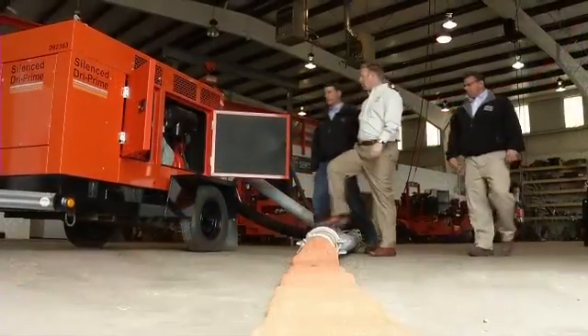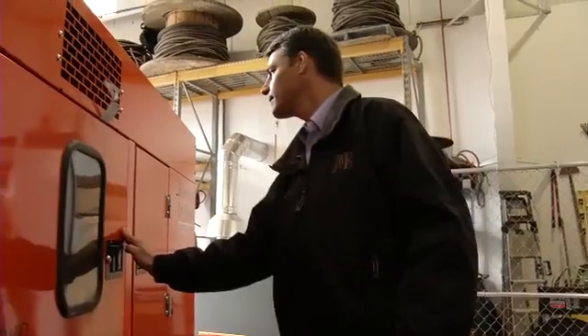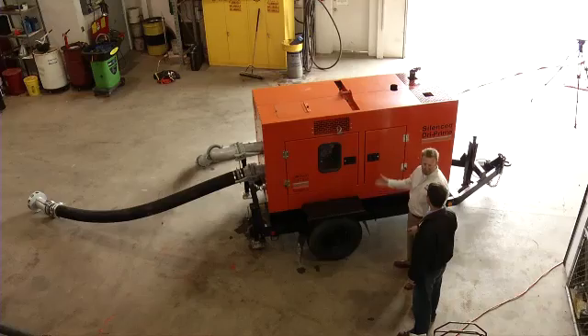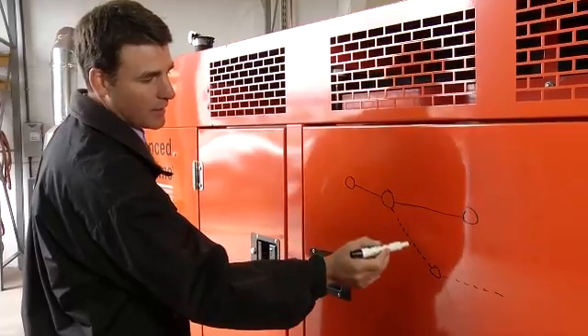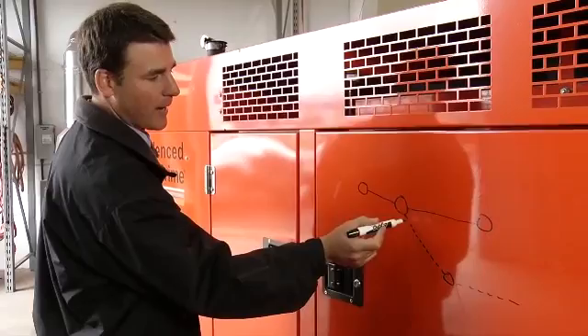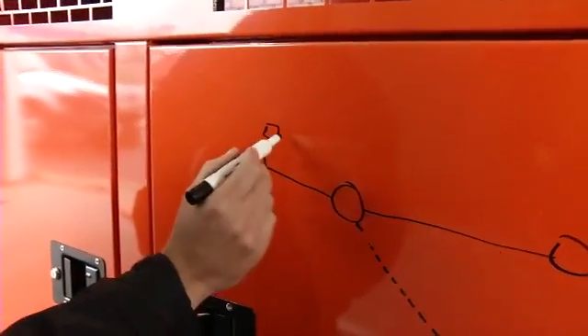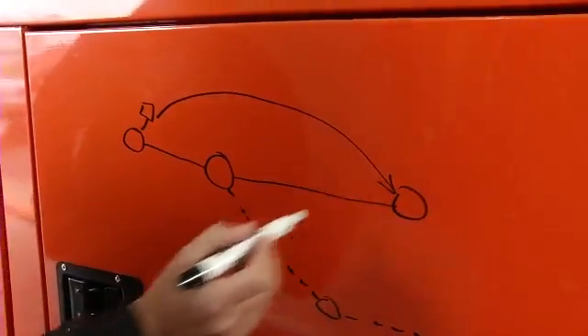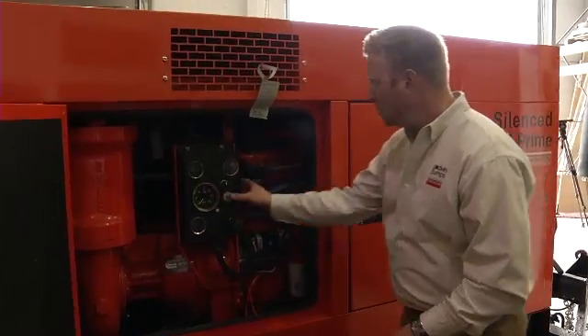This is our CD150 pump — it's a 6-inch pump. To review plans for this process, Mark comes to Godwin Pumps in Woodburn, Oregon. They're responsible for all the systems that will convey sewage around the work areas during the project. The last thing we want is a spill on this project, and so we've taken every precaution to ensure that won't happen. In order for us to make a tie-in to the existing system with our new piping, we'll need to bypass or pump around the existing sewage flowing through the pipe, around our work area, using a temporary pump station and temporary piping. It's complex, and it's like doing open-heart surgery.